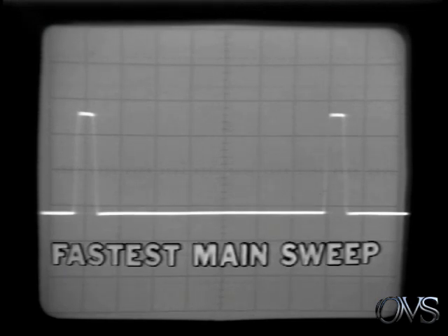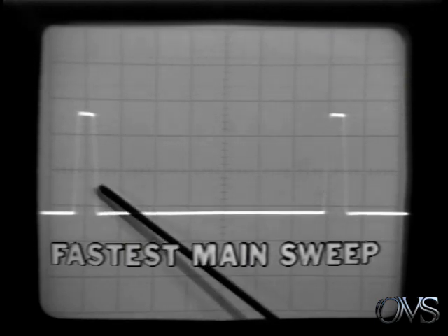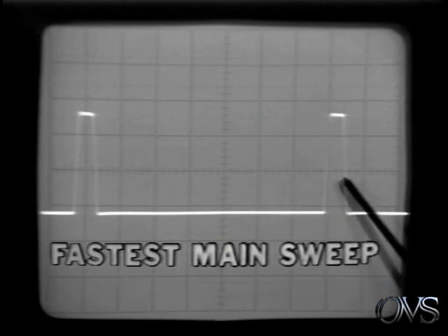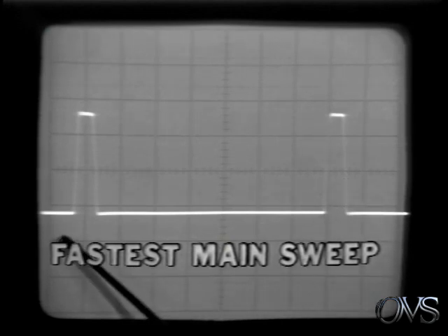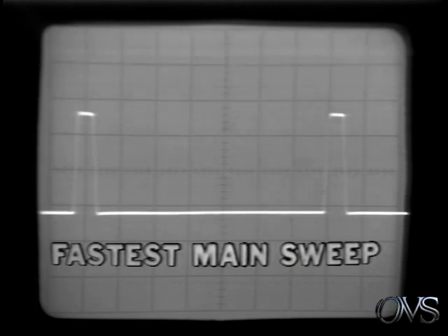This reduces the maximum delay period. The limitation here is that both the beginning and the end of the time interval must be displayed on the main sweep display on the CRT. Otherwise, you could never locate one or the other of the points of the time interval you are measuring using the delayed sweep generator.